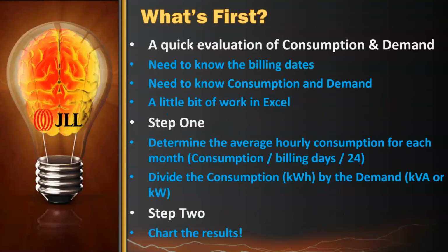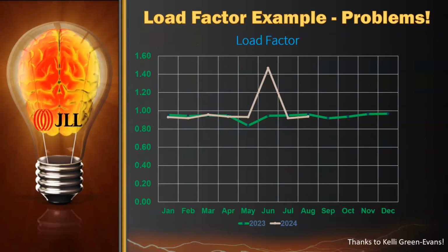Oh, chart the results. Went too far. Got a little too crazy. We're gonna take that chart, and what we're gonna do is say we think a reasonable load factor is 0.75. You're up around 1. The difference between those two is where we think the squeeze is, and maybe the reasonable value is 0.75, so we're going to take you down to 0.78. And what does that mean? This is a data center, and they have several thousand amps going through it, so it's a significant deal.